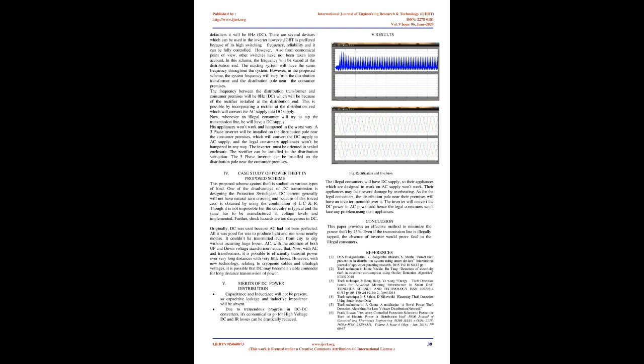This proposed scheme against theft is studied on various types of load. One of the disadvantages of DC transmission is designing the protection switchgear. DC current generally will not have natural zero crossing, and because of this, forced zero is obtained by using a combination of LC and R. Though it is not impossible, the circuitry is typical and the same has to be manufactured at voltage levels and implemented. Further, shock hazards are too dangerous in DC.